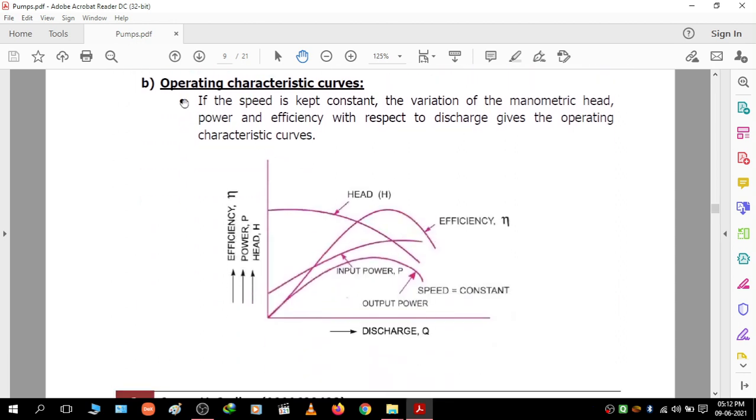Second is the operating characteristic curves. If the speed is kept constant, the variation of manometric head, power, and efficiency with respect to discharge gives the operating characteristics curves. This curve shows discharge plotted against efficiency, power, and head. This is the operating characteristics curve.